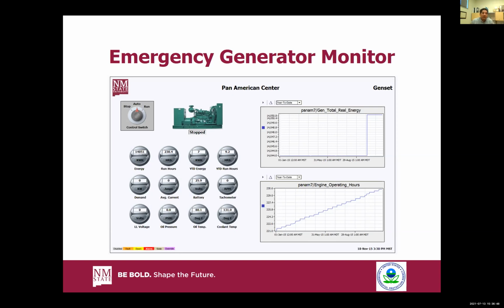This is a way we can be responsible and monitor how often these generators run, since they have to exercise for life safety compliance and fire code - we have to make sure they'll start when needed, so we exercise them weekly. The graph on the right labeled operating hours shows that stair-step over time, a year-to-date window. This one was taken back in 2015, but it shows the generator does exercise.